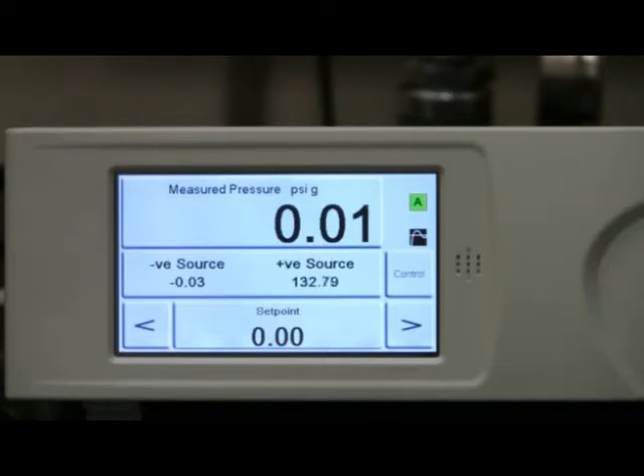The supply pressure should be set to 10% above the full-scale pressure of the installed control module. For this calibration run, we are only controlling positive pressures. If negative gauge or absolute pressures are required, we would need to connect a vacuum pump to the negative supply port.